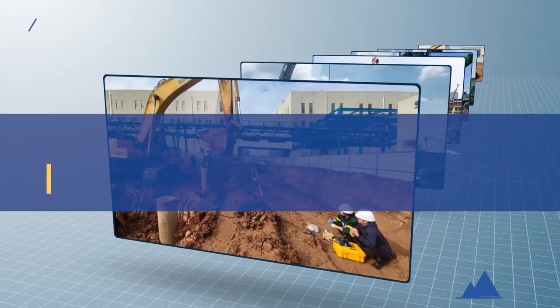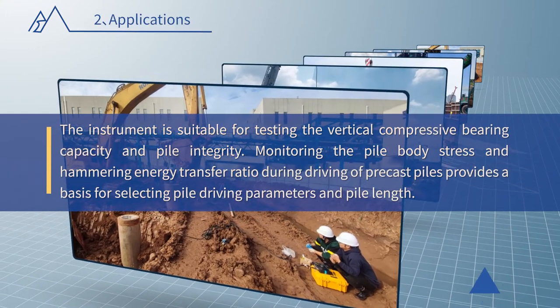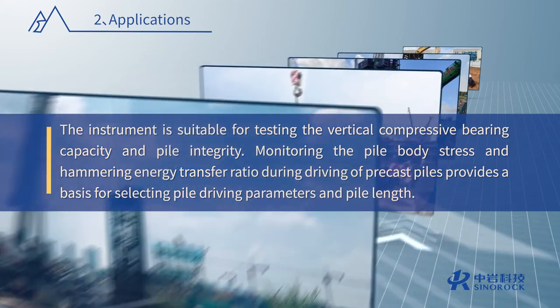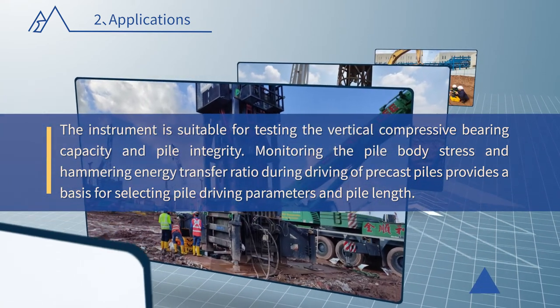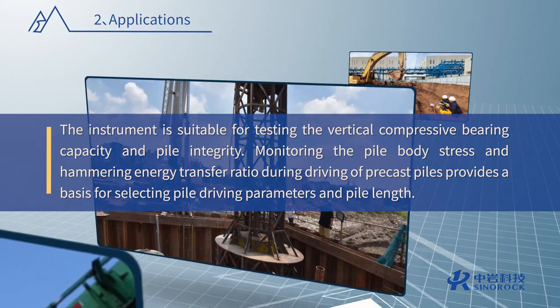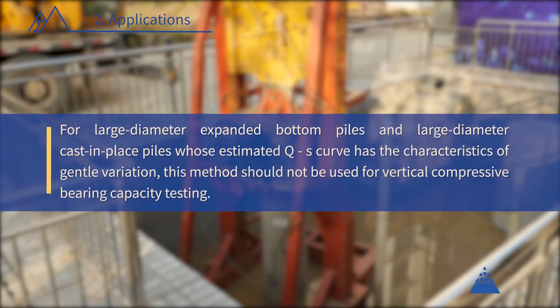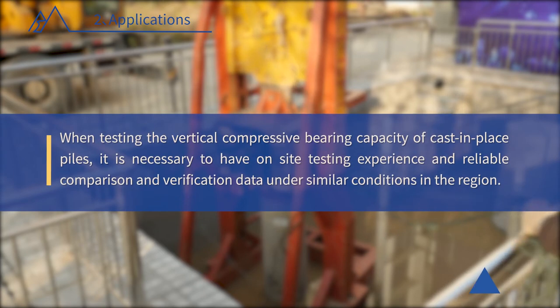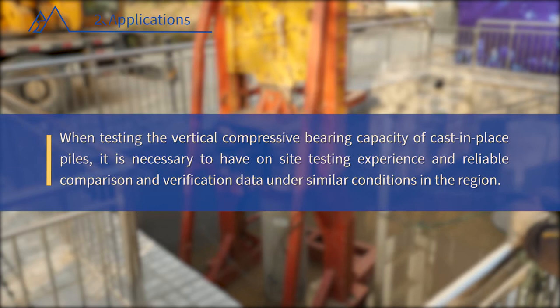Applications: The instrument is suitable for testing the vertical compressive bearing capacity and pile integrity. It monitors pile body stress and hammering energy transfer ratio during driving of precast piles, providing a basis for selecting pile driving parameters and pile length. For large diameter expanded bottom piles and large diameter cast-in-place piles whose estimated QS curve has characteristics of gentle variation, this method should not be used for vertical compressive bearing capacity testing. When testing cast-in-place piles, it is necessary to have on-site testing experience and reliable comparison and verification data under similar conditions in the region.